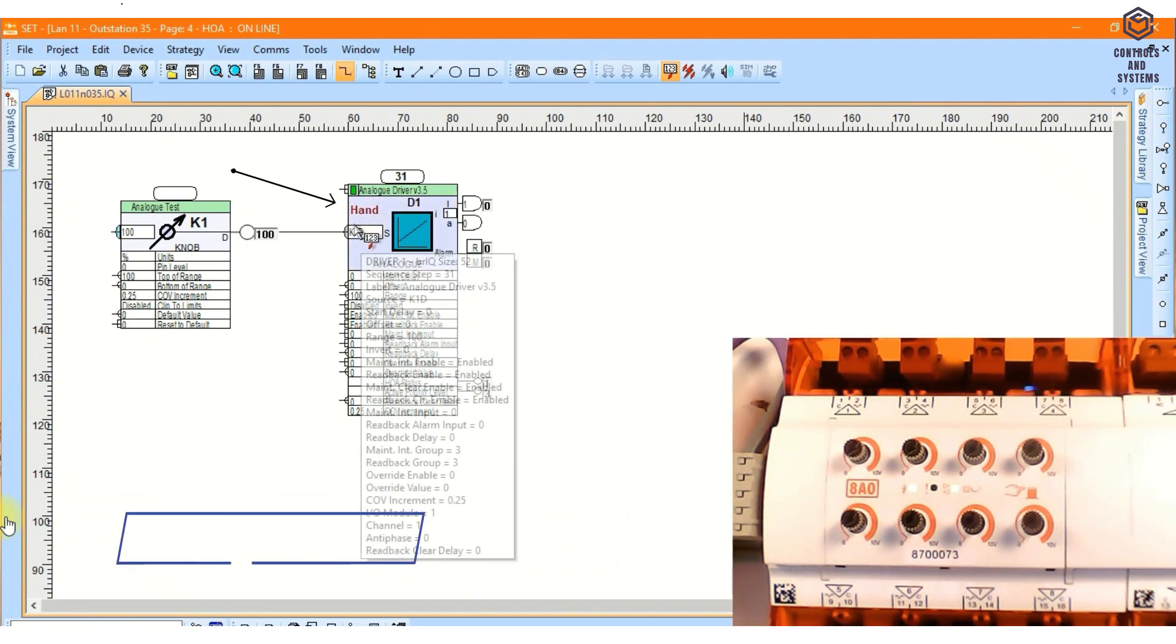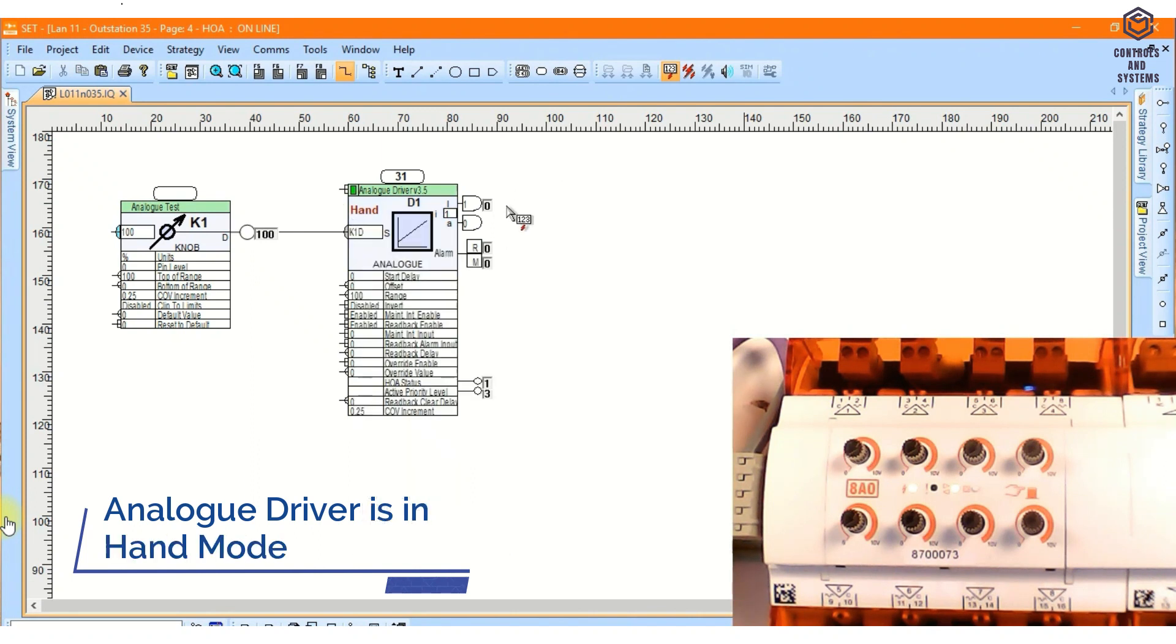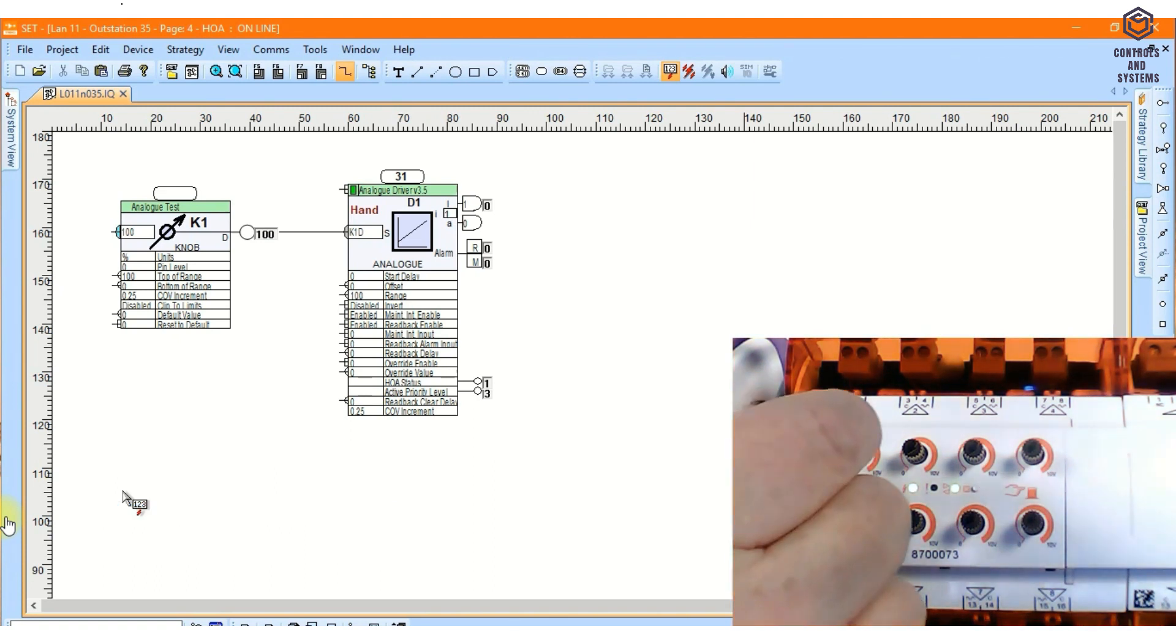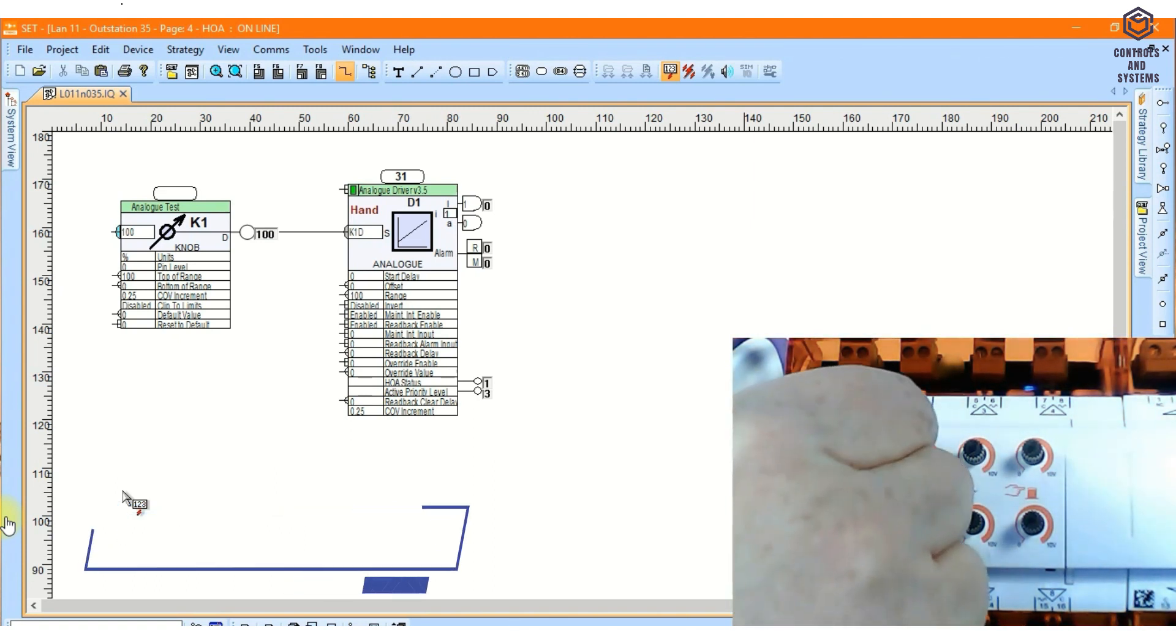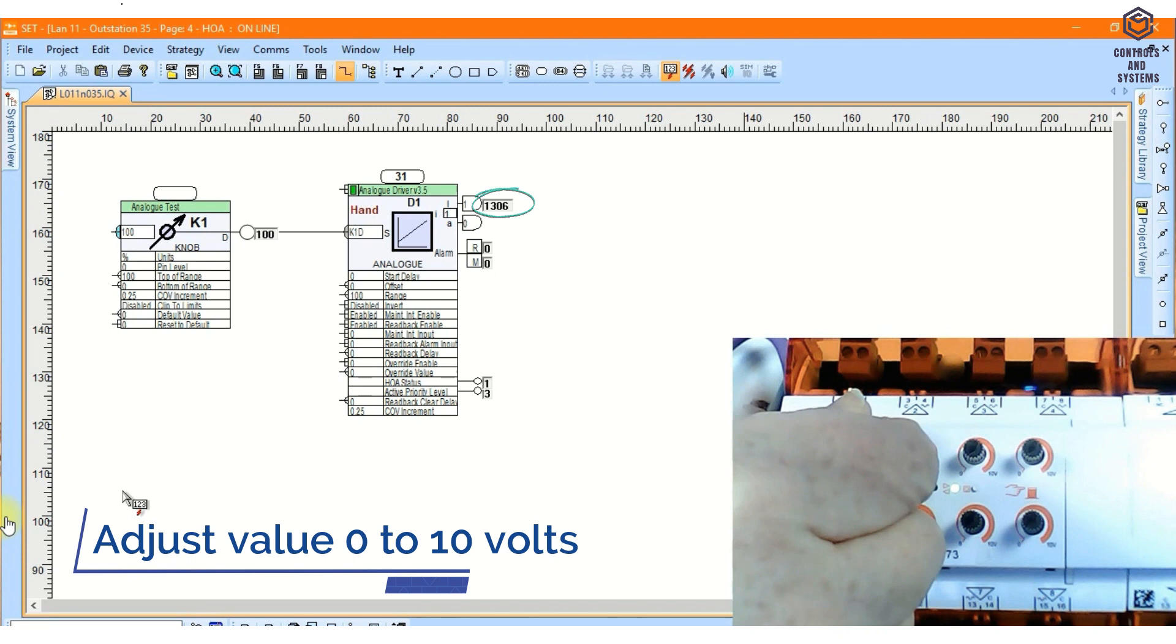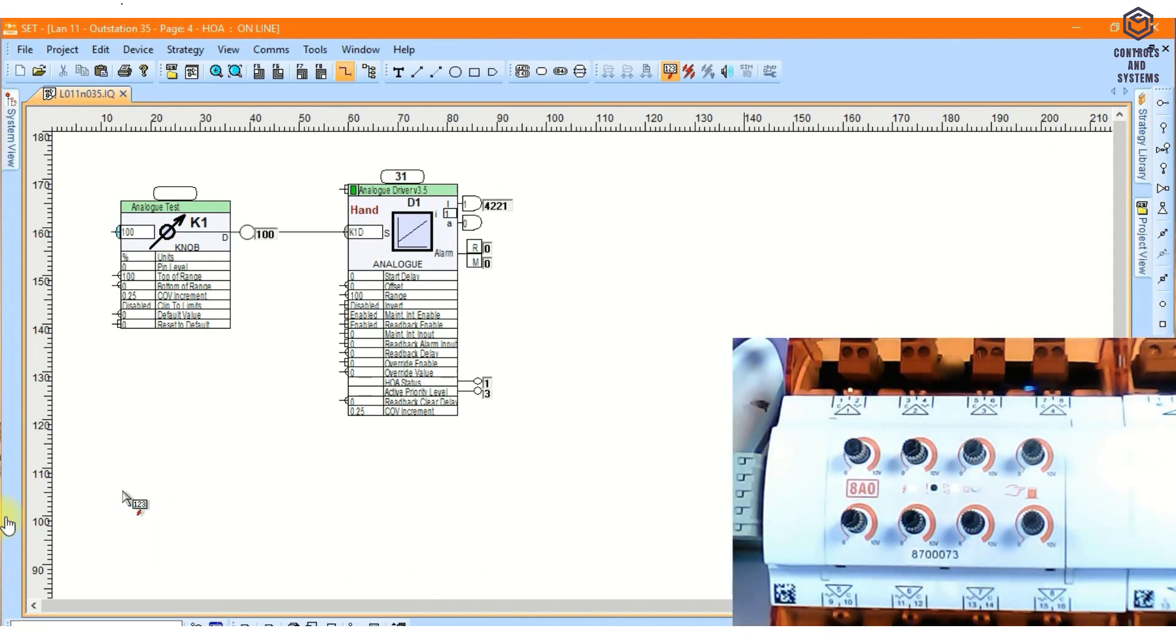The driver indicates hand, and the analog output channel has now gone to 0. Now we can adjust between 0 to 10 volts. Once you change the setting, you can leave the potentiometer on that position until the end. Users can then enable or disable the override as required by pressing the button.